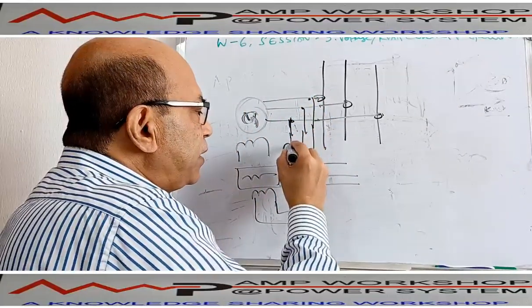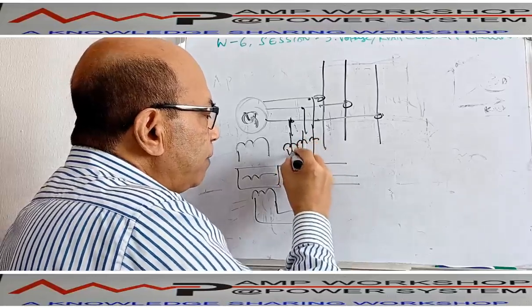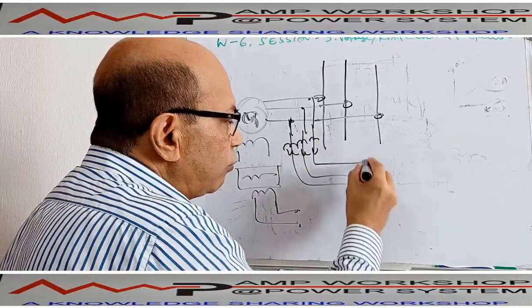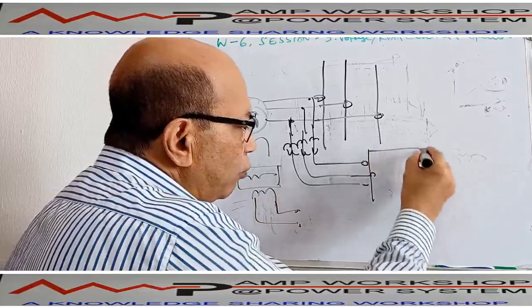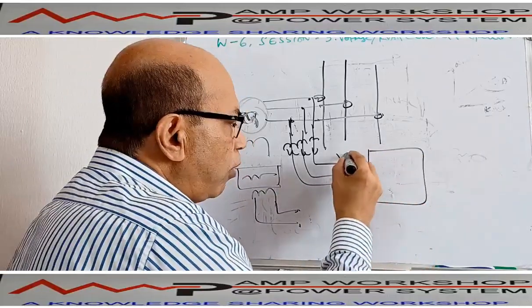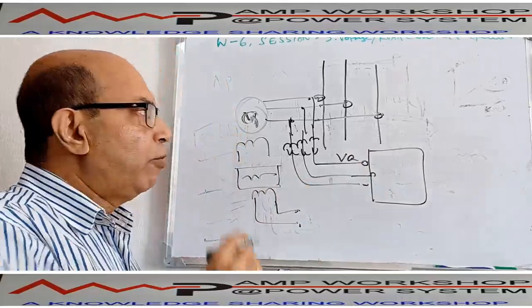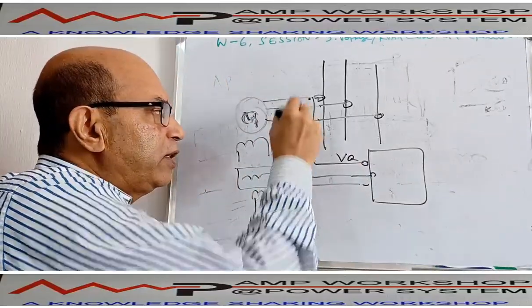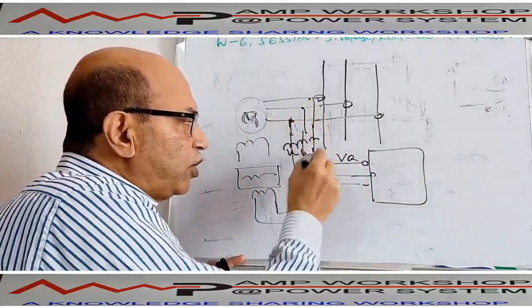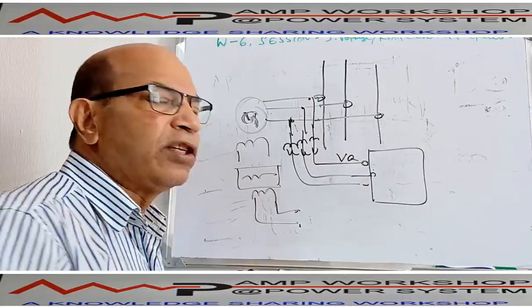We have to use a PT, and the PT output voltage will be coming to the equipment, the controller. So these will give the actual voltage, right? When the generator is rotating, what is the voltage it is producing? We will sense the voltage by potential transformer. We get the voltage input.